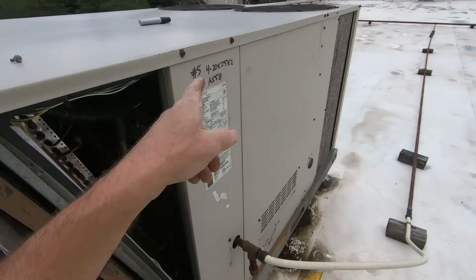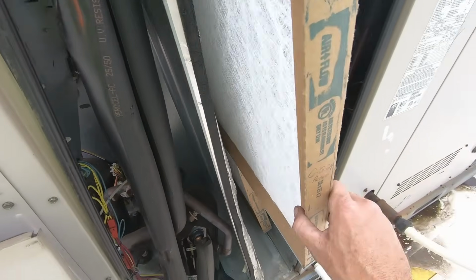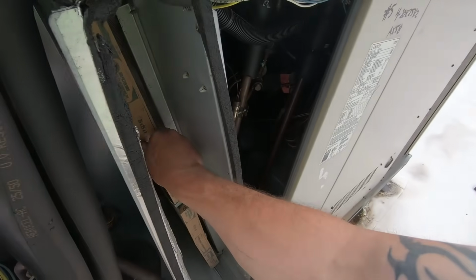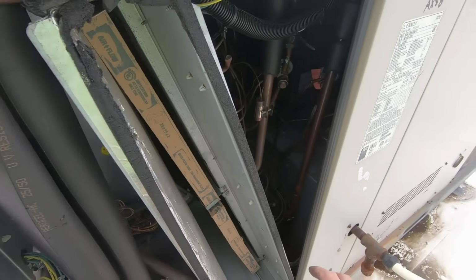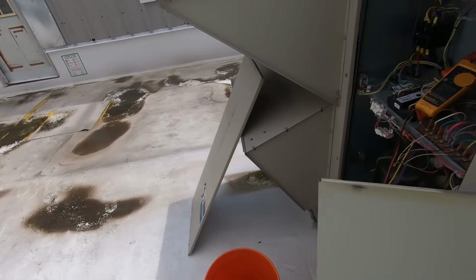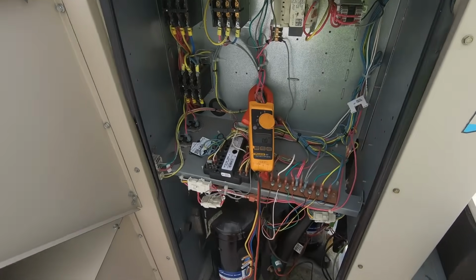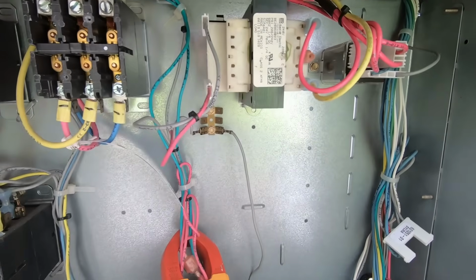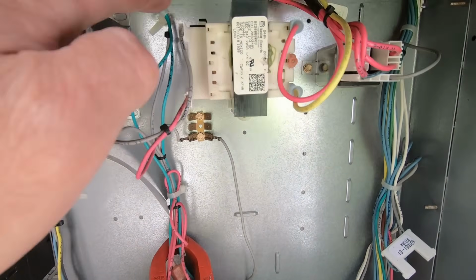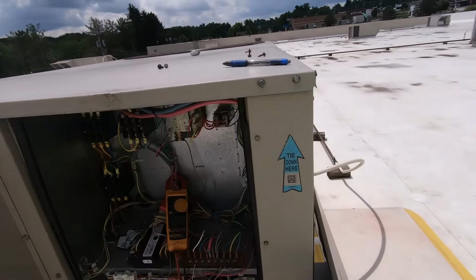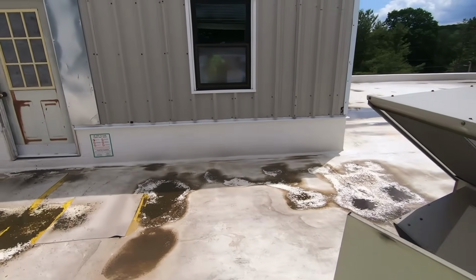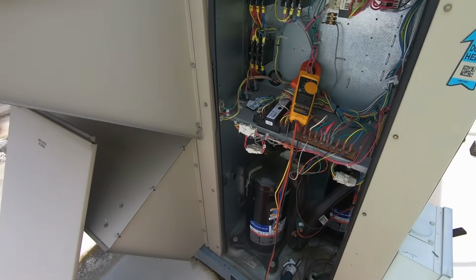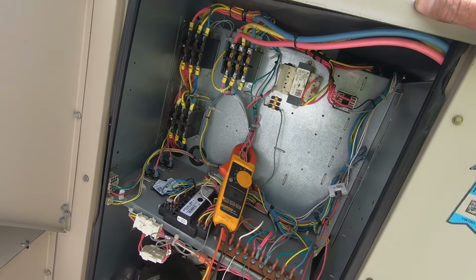Right, I've moved on to number 5 here, and I noticed right off the bat, extremely clean filters. Belt, blower, everything looks okay there. Contactors look decent. And then I find this tripped resettable fuse on our transformer. So let's go ahead and push that and see what happens. More than likely it's gonna immediately trip. What do you got? You gonna trip?